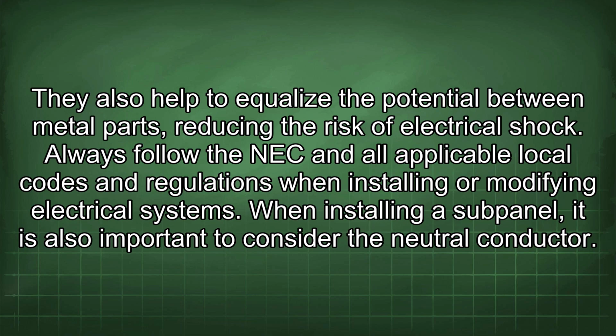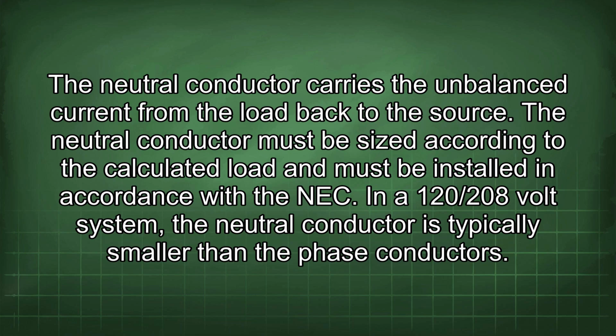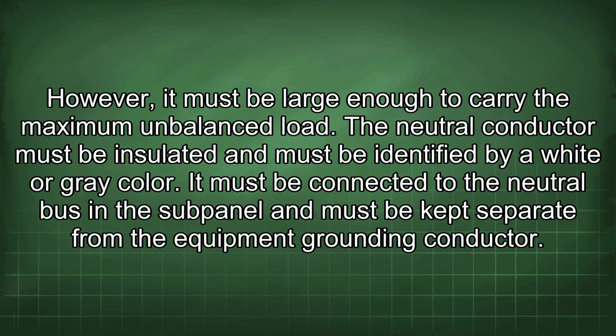When installing a subpanel, it is also important to consider the neutral conductor. The neutral conductor carries the unbalanced current from the load back to the source. The neutral conductor must be sized according to the calculated load and must be installed in accordance with the NEC. In a 120/208 volt system, the neutral conductor is typically smaller than the phase conductors. However, it must be large enough to carry the maximum unbalanced load. The neutral conductor must be insulated and must be identified by a white or grey color.